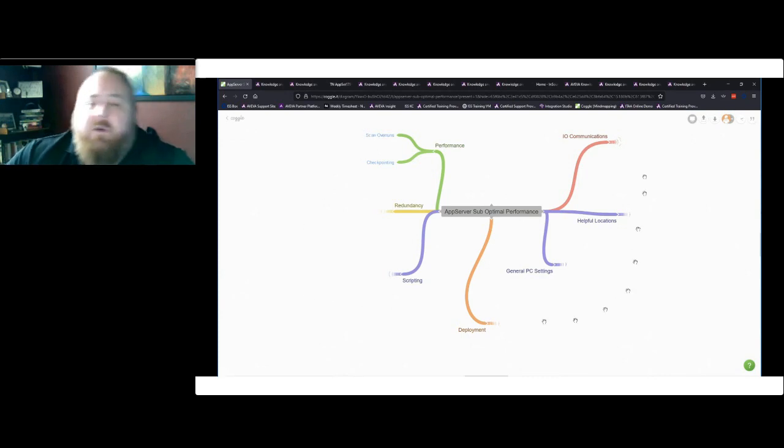And that something going on could be any of the things I talked about. It could be a poorly written script. It could be you're querying a web service and the payload is bigger than what you expect and the script is timing out. It could be the virus protection software has some of our internal file systems locked when we go try to checkpoint a file. So scan overruns are just that. I was supposed to do this in a second, and for whatever reason at 1,002 milliseconds, I said I couldn't do it. I kicked out execution.